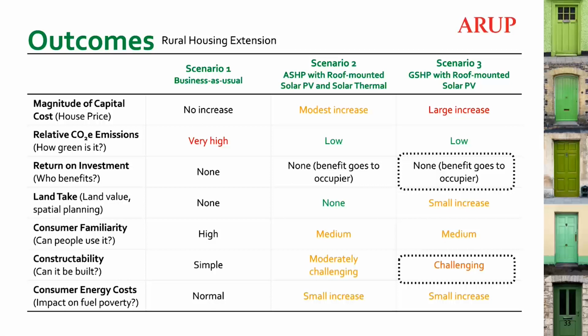In summary: the building integrated ground source heat pump presents limited opportunity for return on investment for developers compared to the ambient loop, which offers more of a business case opportunity. Although implementing ground source heat pumps would be challenging in practice, particularly at scale and associated with ground heat recovery infrastructure, we found it would on the whole be slightly less challenging than an ambient loop approach, which requires cross-party collaboration at scale.